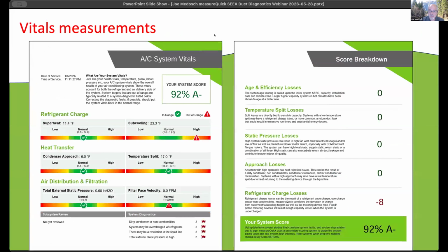This is what you're going to get out of MeasureQuick. You're going to get a score based upon the measurements that we took from all of our probes. They're giving you refrigerant charge and heat transfer, air distribution, whether or not your refrigerant's working well, and whether your airflow is also working well based on our measurements. You can use the TrueFlow grid, or we have our own method for measuring airflow with psychrometers. But in general, now I have an actionable number and an actionable report to talk to my client about what things we need to be doing.